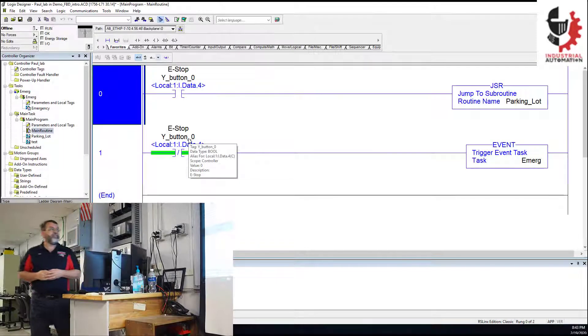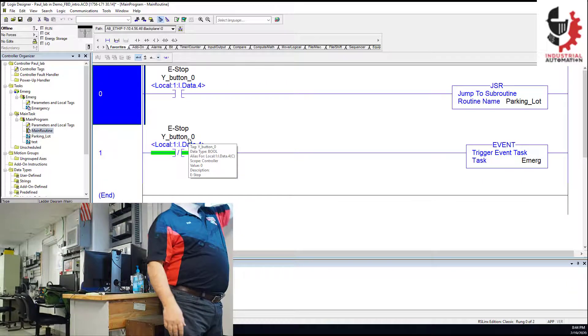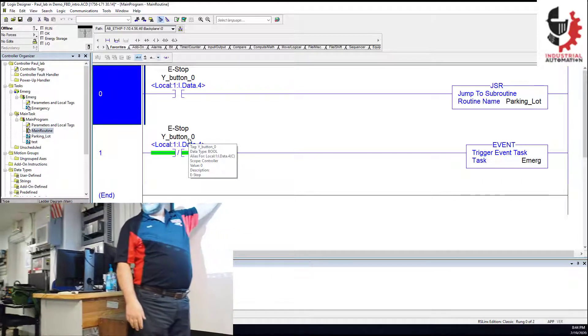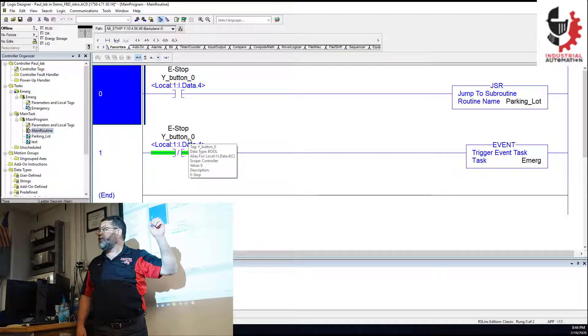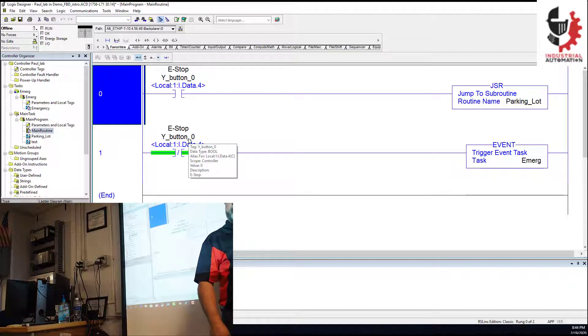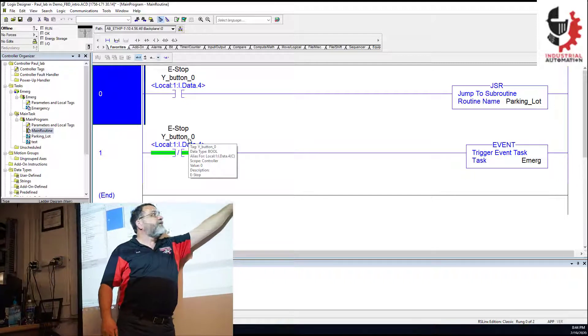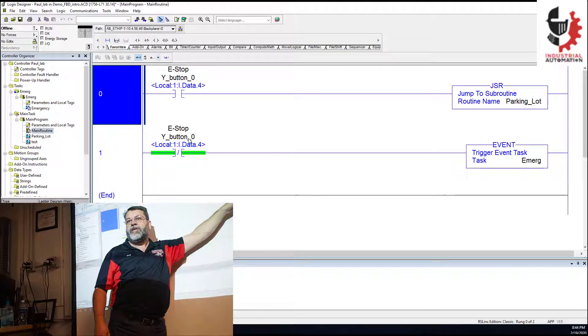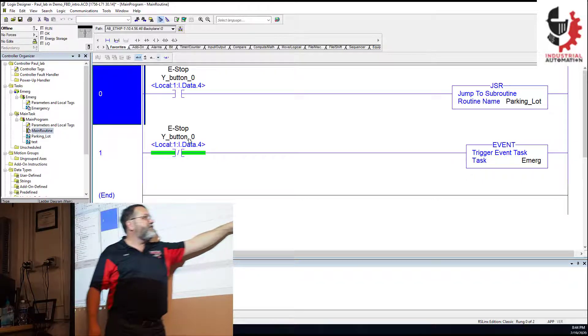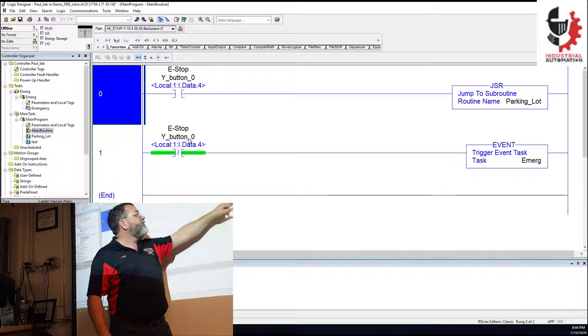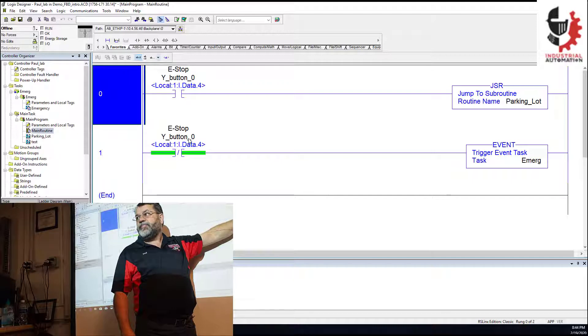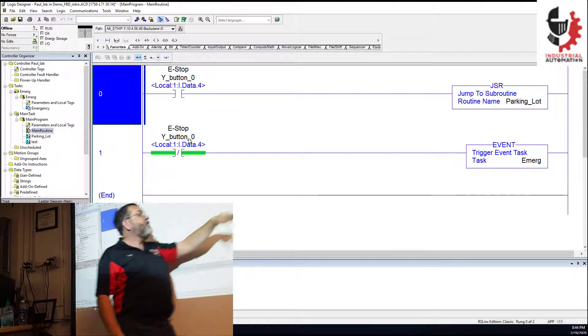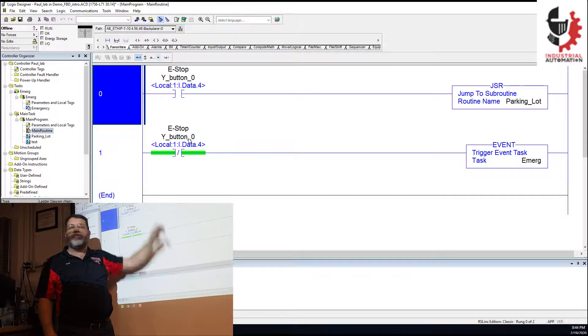So this is kind of like my introductory screen, my main control. What I'm seeing here is that if I don't have the e-stop hot, as in its normal position, normally hot, then I'm going to jump to a subroutine called parking lot. But if I hit the e-stop, I'm going to lose this signal so the parking lot subroutine won't work anymore, and it's going to send me to this emergency event task. So notice this is a jump to subroutine. This is an event trigger. So there are two different things going on. This is the only ladder logic that I'm going to use in this project.